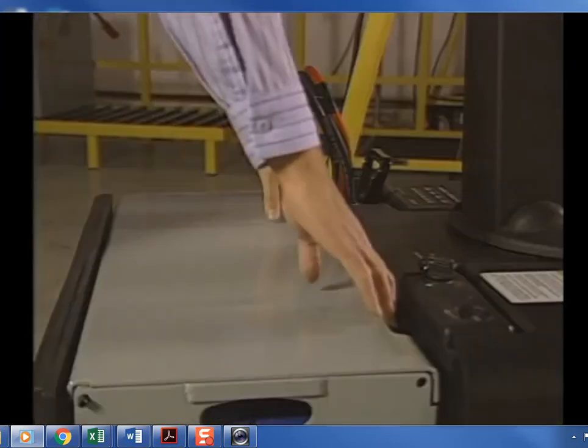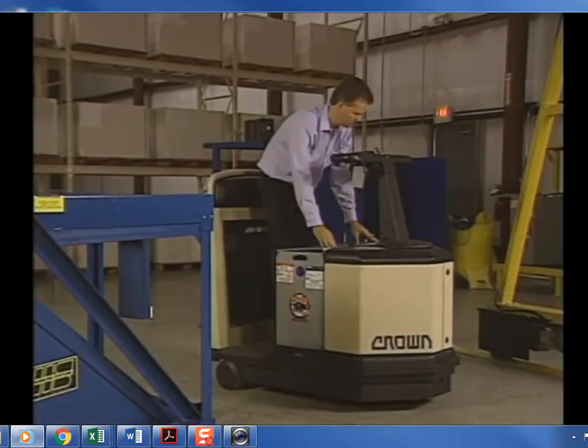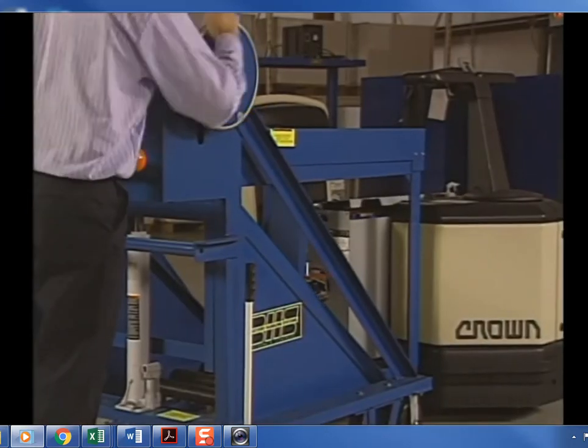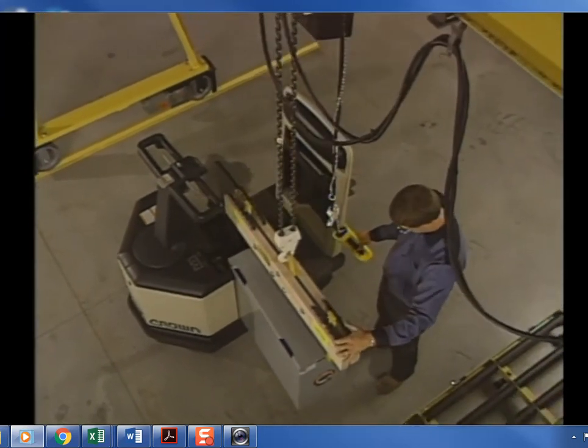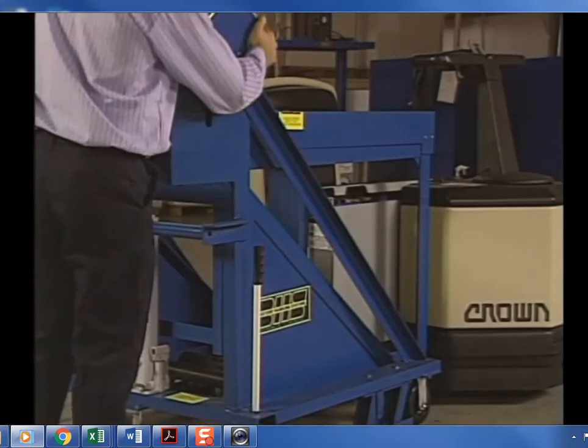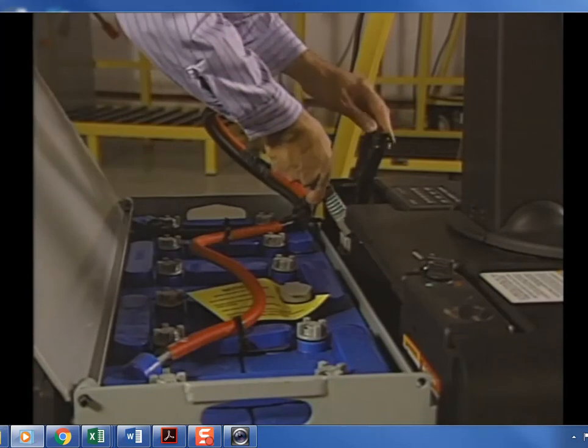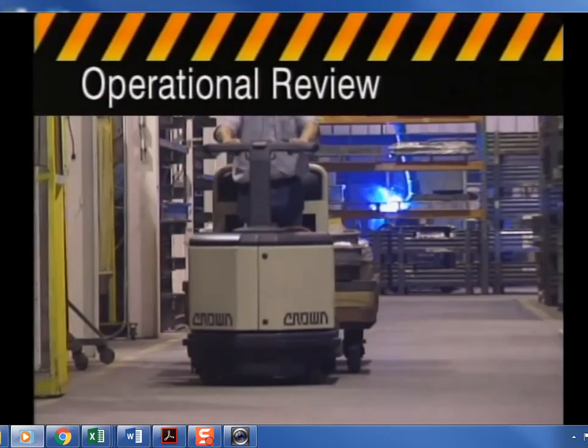To change a battery, park the truck on a level surface in the battery changing area, turn the truck off, and apply the brake. Disconnect the battery and lay the connector inside the battery cover. Remove the retainer plate, position a battery stand at the correct height next to the truck, and roll the battery out — or use an approved hoist and spreader bar to lift the discharged battery and replace it with a charged battery. Never let metal objects contact the electrical connections on the top of the battery. Install the correct voltage, size, and weight battery, replace the retainer plate, and reconnect the battery.